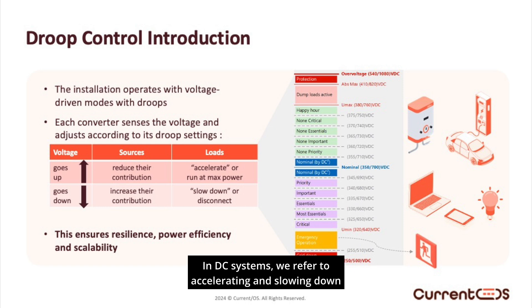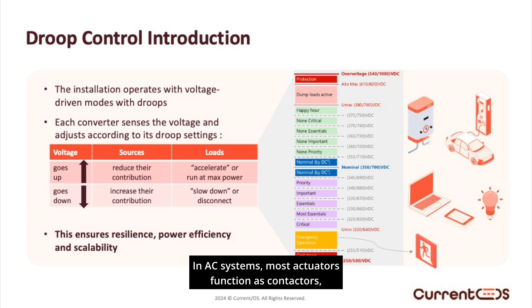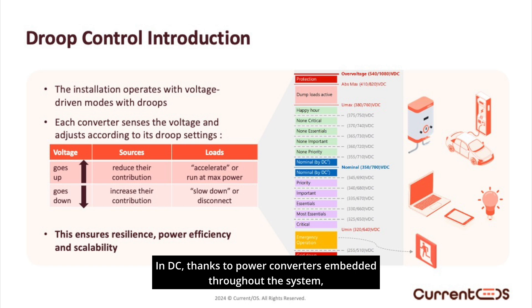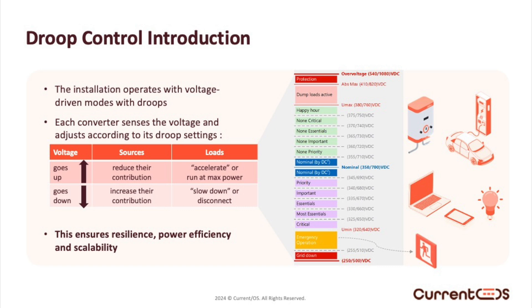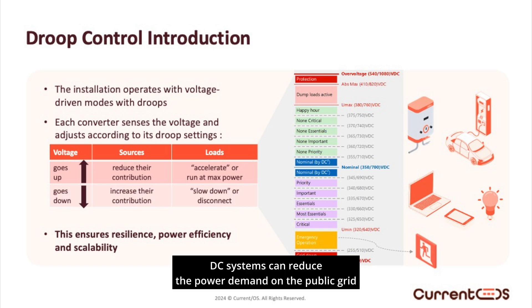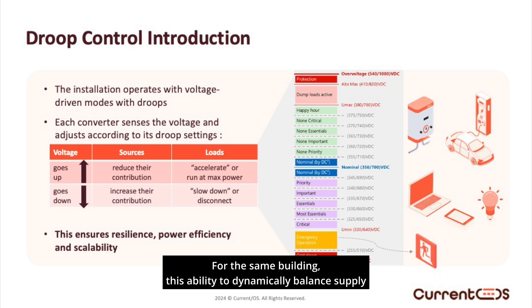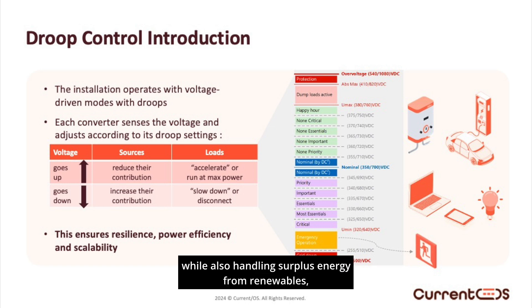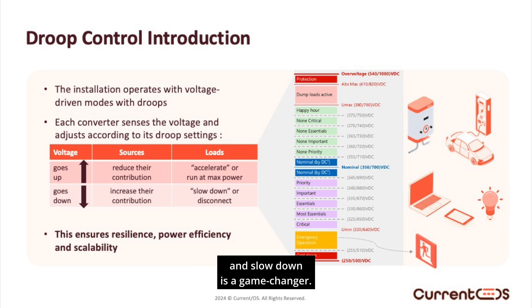In DC systems, we refer to accelerating and slowing down to describe the dynamic adjustments of power flow. This highlights a key difference between AC and DC. In AC systems, most actuators function as contactors, toggling between on and off — think about the day-night switch for a water heater: it's either on or off. In DC, thanks to power converters embedded throughout the system, every source and load effectively has its own variable speed controller, allowing for gradual, precise adjustments. By continuously adjusting sources and consumers, DC systems can reduce the power demand on the public grid by at least half, and sometimes up to five times, drastically lowering the required power at the grid connection point. In a world where public grids struggle to meet the rising demand for EV charging while also handling surplus energy from renewables, having a system that can continuously accelerate and slow down is a game-changer.